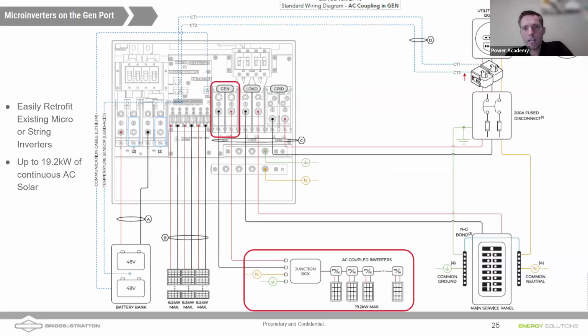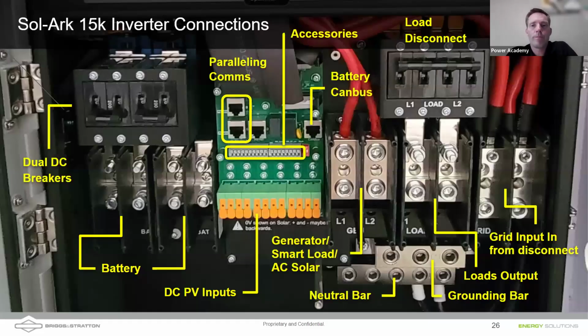Okay, so let's take a quick look at a wiring diagram. This is from a Sol-Ark 15K showing those microinverters coming in through the gen port on the inverter. And I'm also going to show what this looks like. So the generator port is right here on a Sol-Ark 15K. Your battery connections are, of course, here on the left side, and you'll want to make sure that you use both of those dual terminals on a Sol-Ark 15K if you're using a 15K.